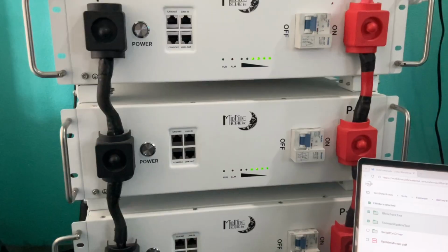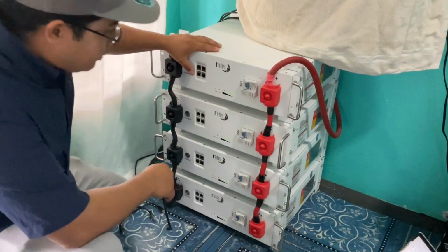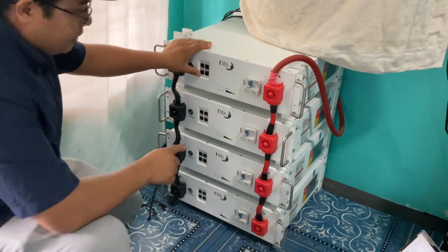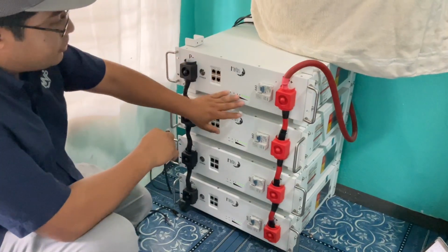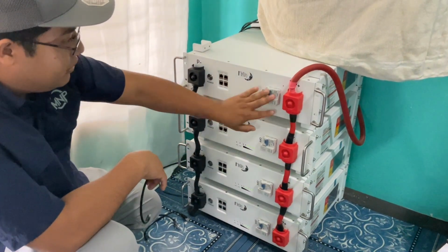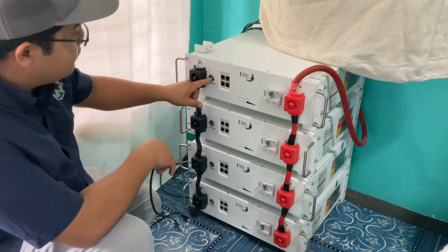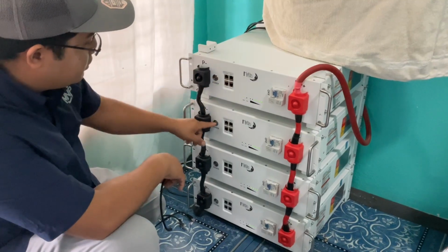So to do this, when you have multiple batteries in a stack, you can update them all at once. So we need to connect the cables from battery to battery, to put the batteries in communication. We want to make sure that all the batteries are turned off, the breakers don't matter in this case. You just want to do a 3-second hold on each battery.